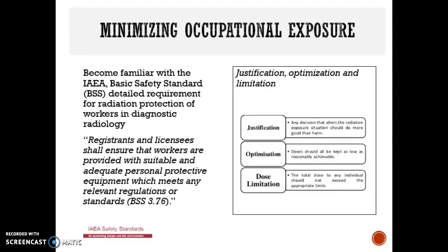It is your responsibility as a technologist to become familiar with the IAEA Basic Safety Standards that provide the guidelines for justification, optimization, and dose limitation. The optimization starts at the X-ray room planning, design, and construction stage, ensuring that doses are kept low by applying a protective barrier between yourself and the patient, like a control booth and lead-lined walls and doors, all of which can keep the dose as low as possible to yourself.